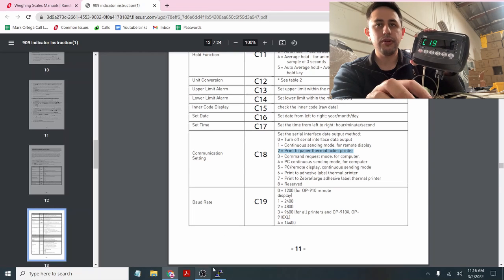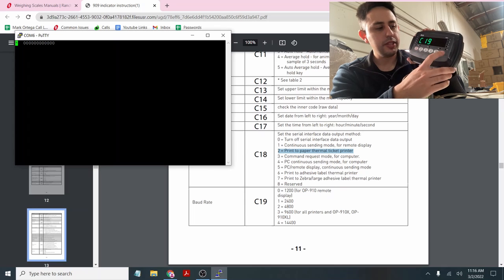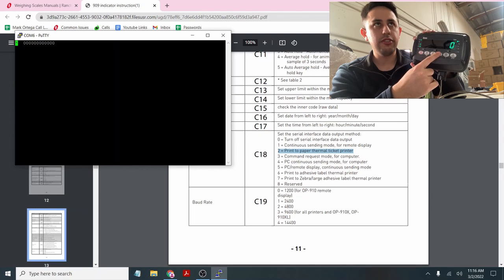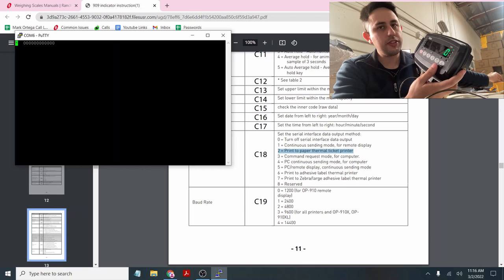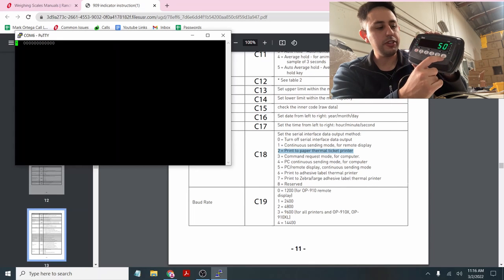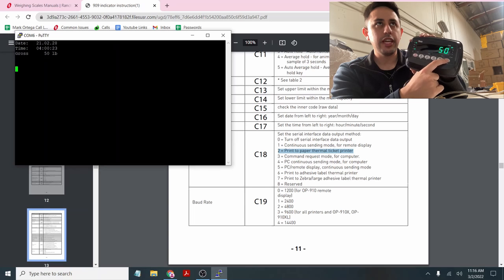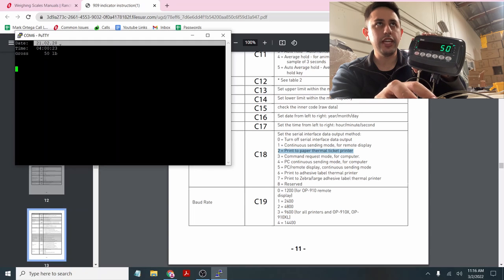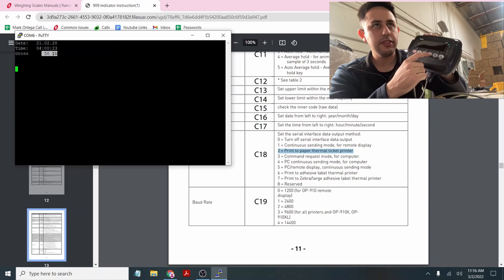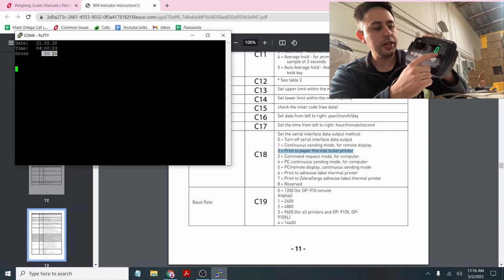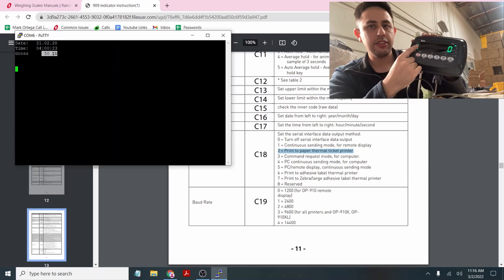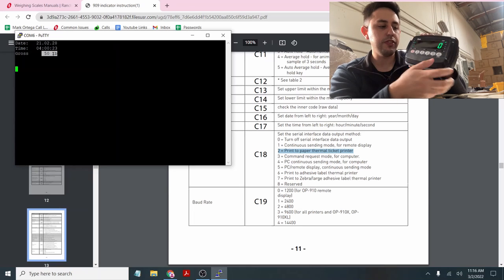So let me just show what's going to show up on the hyperterminal. And then you press escape. So right now it's 0. I could add weight to the scale. 50. Nothing shows up on the terminal because I need to press print. And then now you see the date of the device, the time, and the gross weight. And if I tared whatever weights on it, it's now in net weighing mode because I tared off 50 pounds.